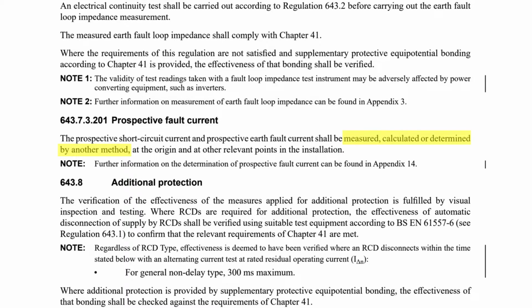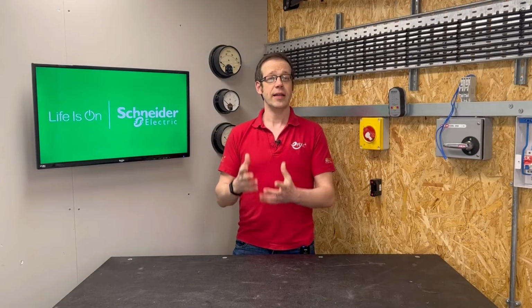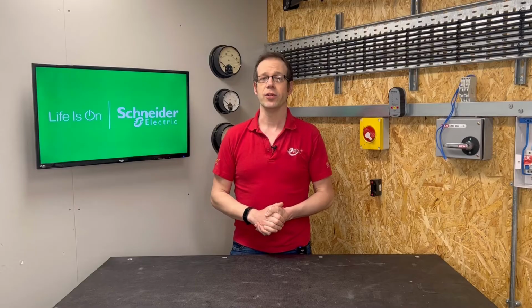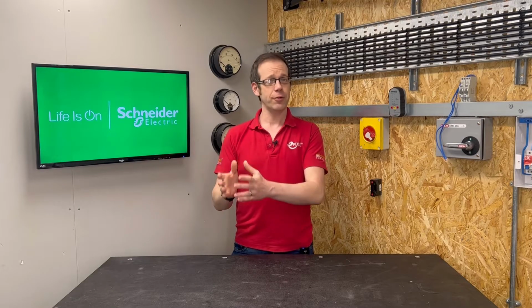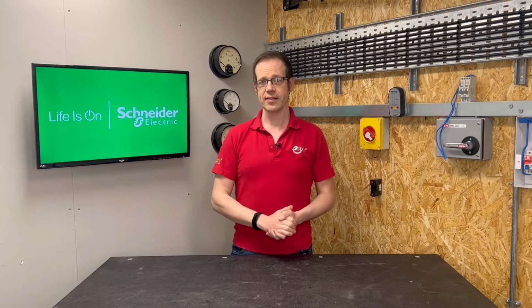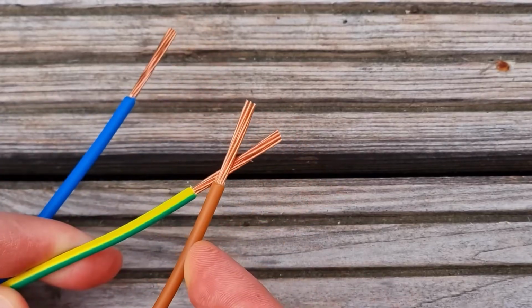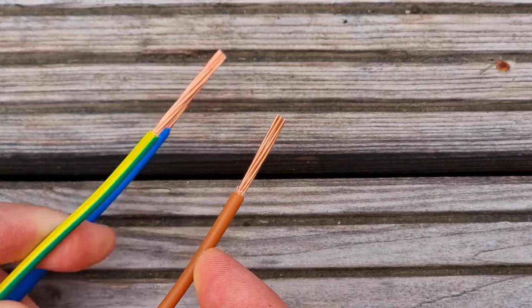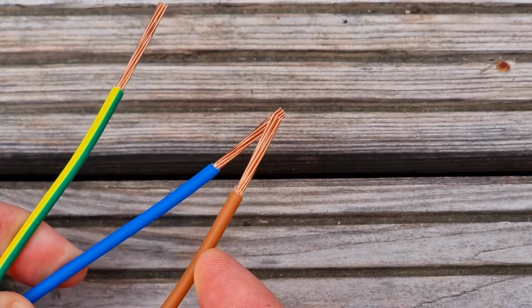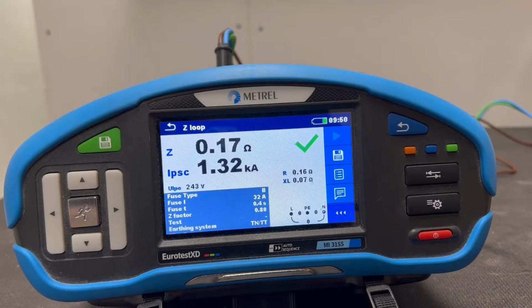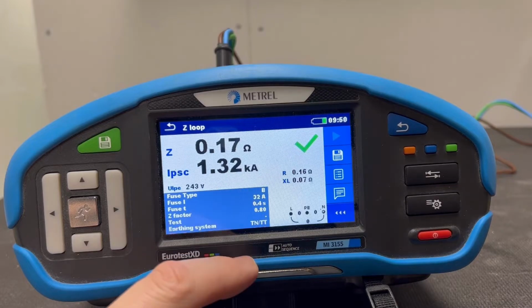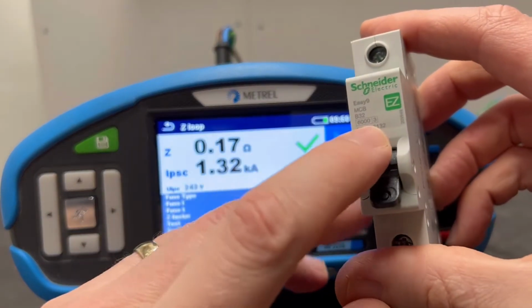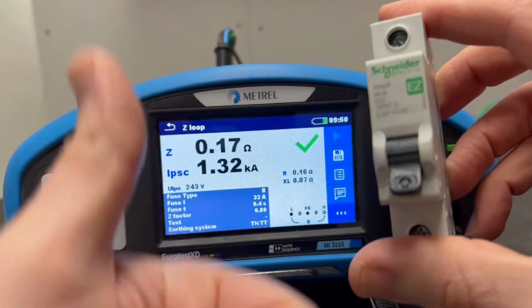If we look at these options further, the first option is measurement. As this is a live test, suitable precautions and test equipment should clearly be used. On a single phase supply, such as most domestic installations, both the prospective earth fault current, aligned to earth fault, and the prospective short circuit current, aligned to neutral fault, should be measured, and the highest value recorded and compared to our circuit breakers to ensure it's lower than the rating of the protective device you are installing.